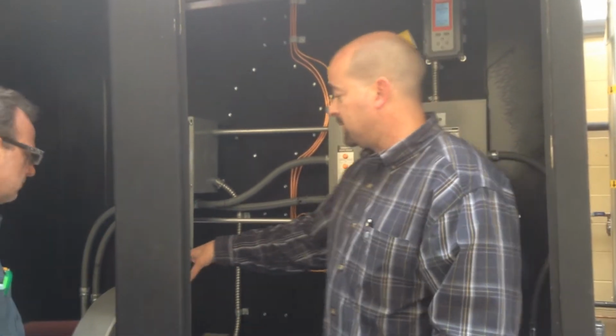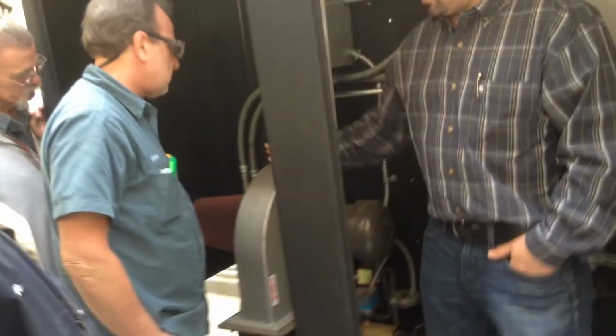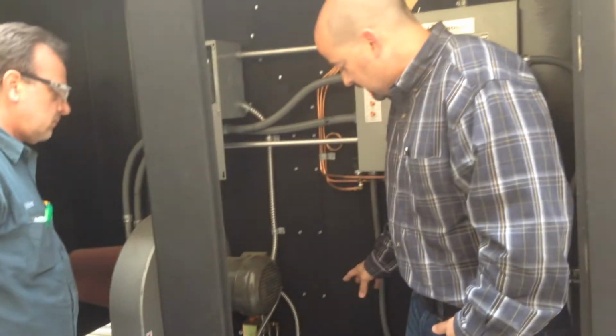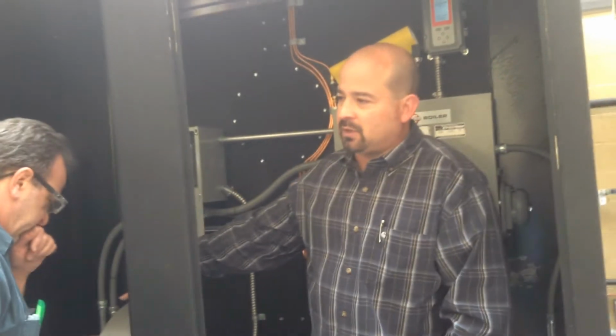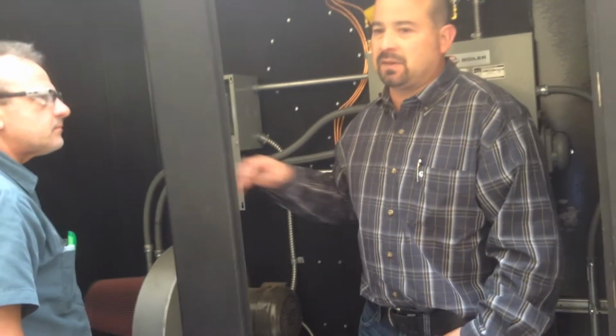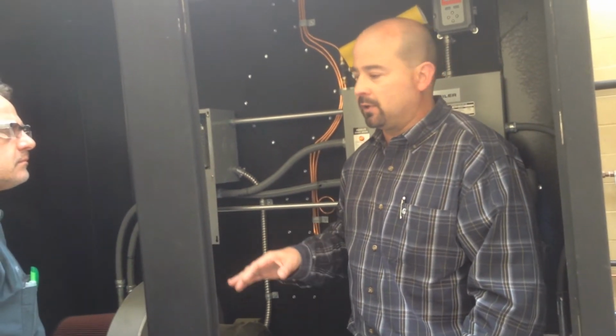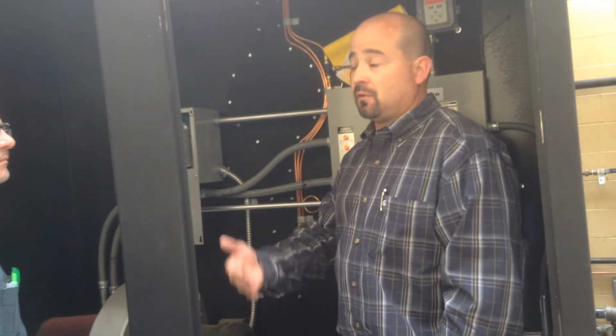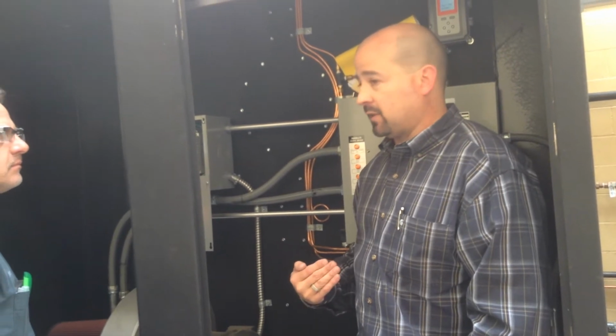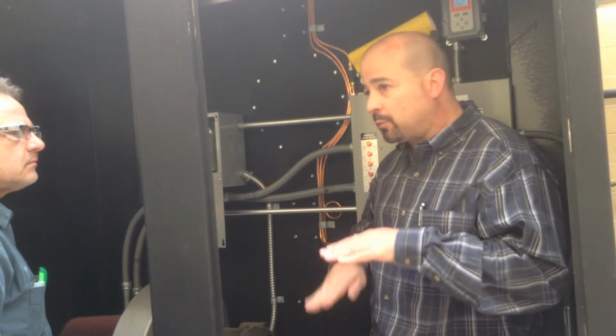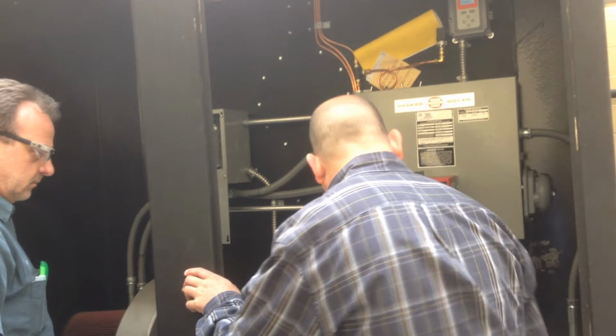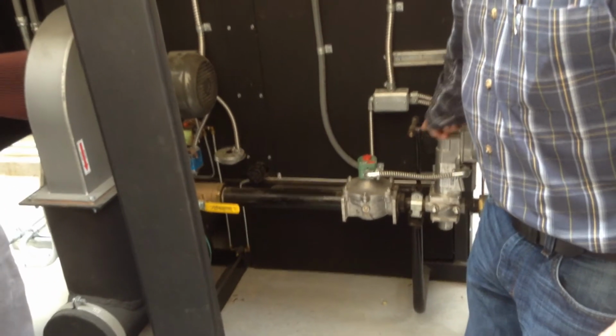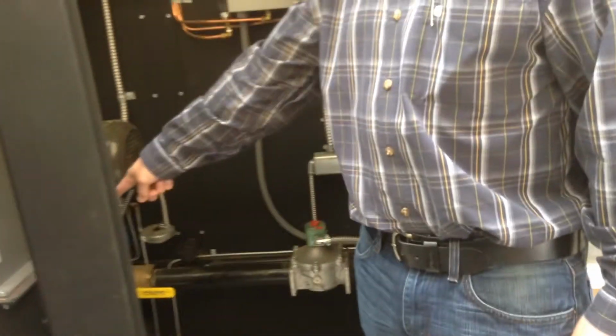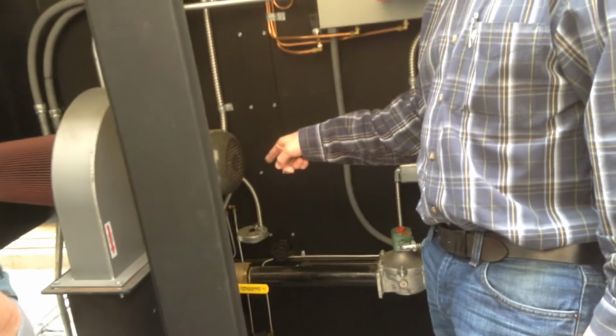The nice thing about this is this has a filter. And the way this system works is if that filter were to get dirty, it doesn't mess up your combustion at all. Whereas with a lot of boilers, if the filter's dirty, then you're going to go fuel rich. You're not going to go fuel rich on this because this works on a ratio principle. So this valve here, the Siemens valve, has an air sensing line, and the air sensing line comes off of it, and it's monitoring the discharge pressure of the blower.